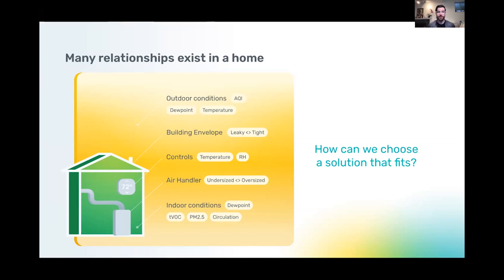So some level of continuous ventilation is important in order to get rid of those, or else we're breathing them in. And if we don't have any way of exchanging the air with outdoor air and ventilating, those build up to harmful, toxic levels that we're chronically breathing in for years and years and potentially decades. And while that may not cross a level of urgent toxicity on any sort of chart, over time it does have a chronic effect, taxing your immune system and your body's ability to solve other problems that it should be solving, because it's distracted by all the chemicals and all the repair it's having to do from all the chemicals.